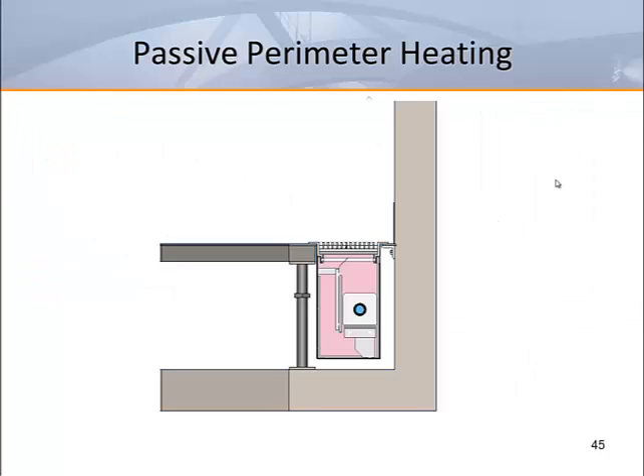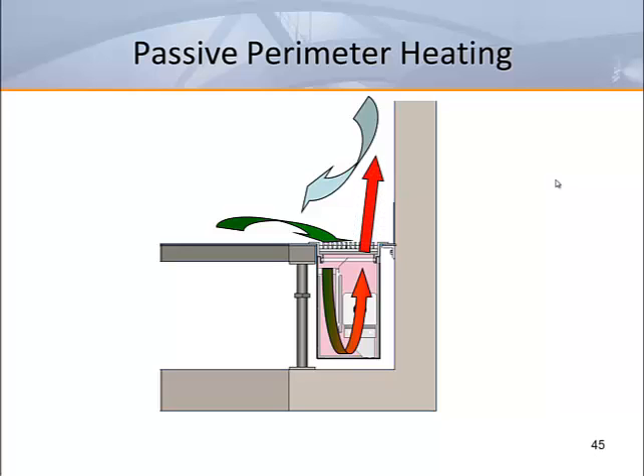Cold convection currents flow down the glass. Room air is induced into the front of the unit. The mixture of air is induced into the plenum and is warmed up as it passes over the fin tube heater. Warm air rises up the glass through convection, totally independent of the cooling system as required by ASHRAE standard 90.1.